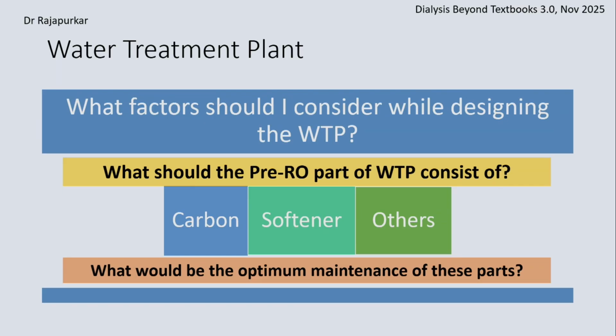Deionizers, it is a good idea if you're going to have them, and I've used deionizers for 40 years plus. It's a good idea to not only have a cation resin and anion resin, but add a mixed bed to it. That way you will be able to get correct water. So, regeneration system, conductivity meter at each place, somebody reading and writing it down, that is required.